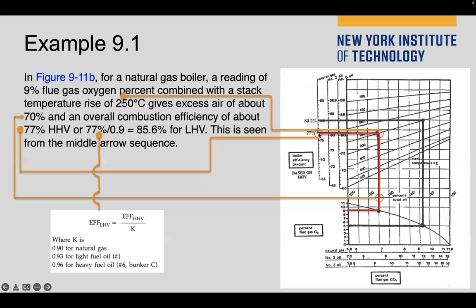It's 77%. It's the efficiency of the high heat value, okay, not low heat value. But if you want to find out the low heat value from the equation, that is the efficiency of the high heat value over K. K is a constant, which also depends on the fuel you used. Let's say natural gas is 0.9, then 77% divided by 0.9 gives you 85.6% of LHV, that is the low heat value, okay?